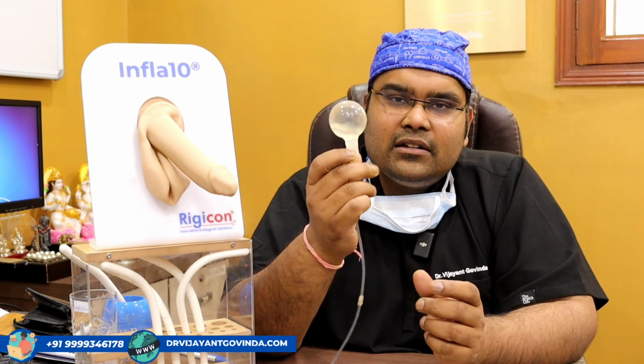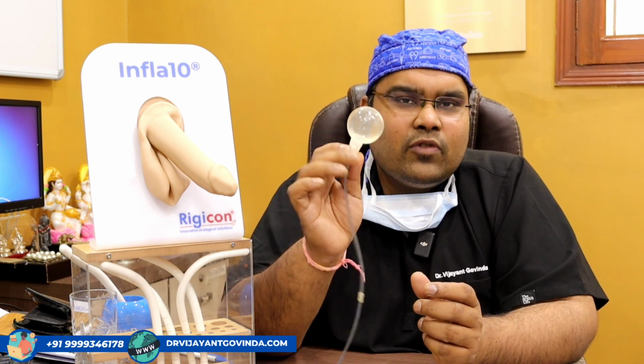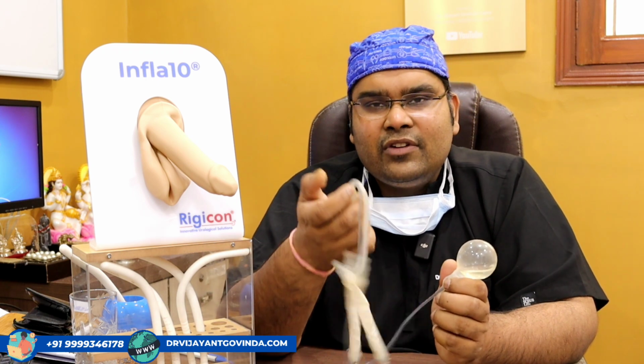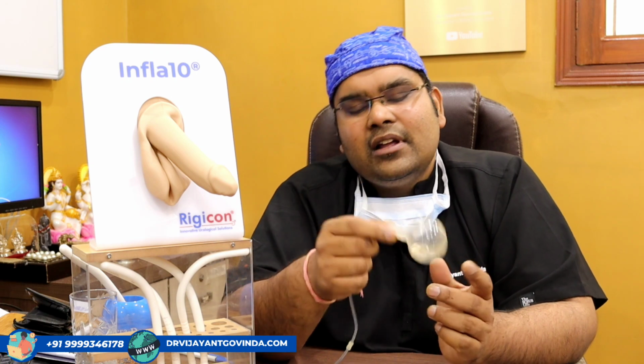The one extra advantage that the Infla 10AX has in terms of the reservoir is the auto-inflate lockout valve. The AMS has a lockout valve at the level of the pump, the Coloplast has a lockout valve at the level of the reservoir, and the Infla has chosen to give the lockout valve at the level of the reservoir.